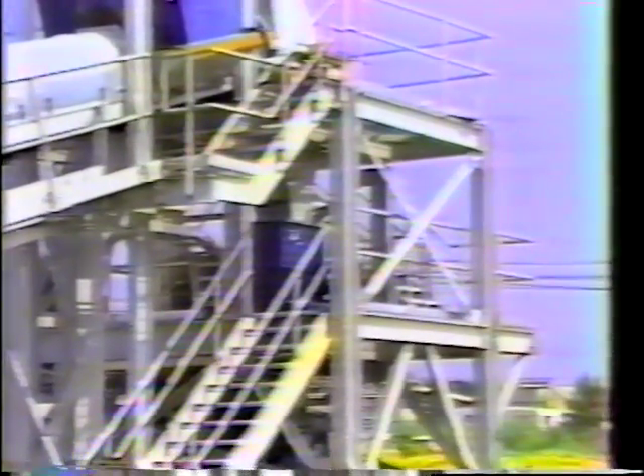Since the coke will be purchased unprocessed, we may receive pieces up to six inches in diameter, and a pulverizer cannot accept anything larger than one inch in diameter. Therefore, a crusher has been provided to ensure that no oversized material will be fed to the pulverizer. This shows a typical sample of the pre-crushed coke.